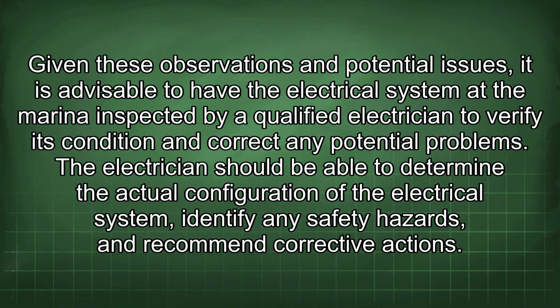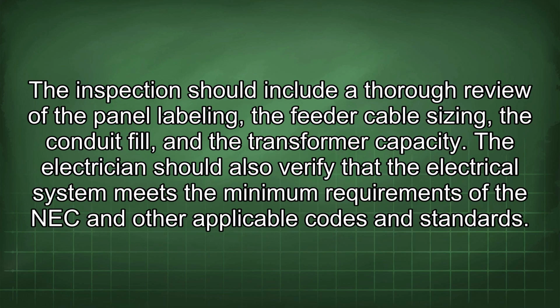Given these observations and potential issues, it is advisable to have the electrical system at the Marina inspected by a qualified electrician to verify its condition and correct any potential problems. The electrician should be able to determine the actual configuration of the electrical system, identify any safety hazards, and recommend corrective actions. The inspection should include a thorough review of the panel labeling, the feeder cable sizing, the conduit fill, and the transformer capacity. The electrician should also verify that the electrical system meets the minimum requirements of the NEC and other applicable codes and standards.